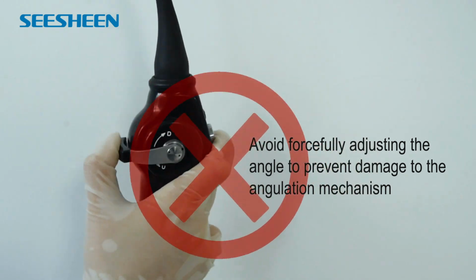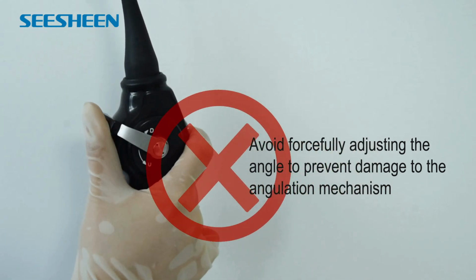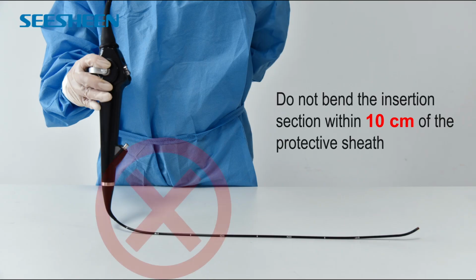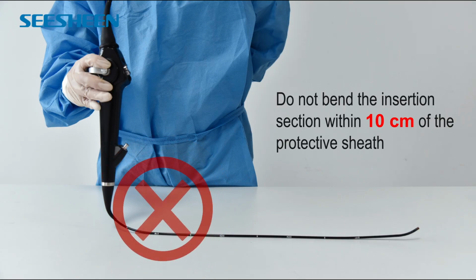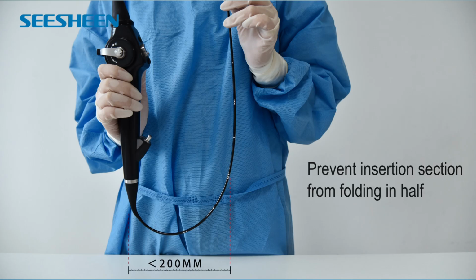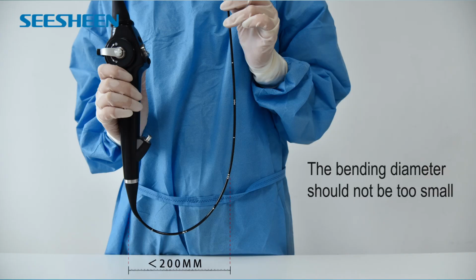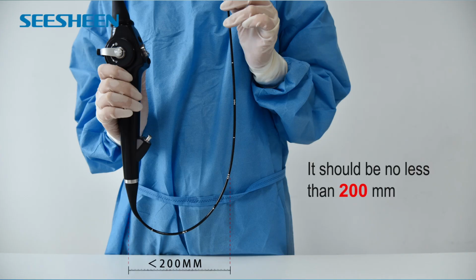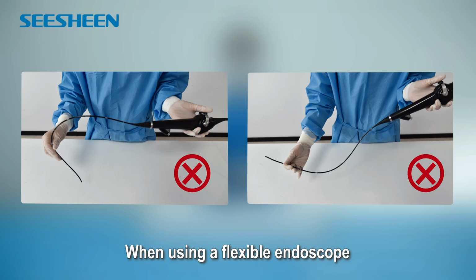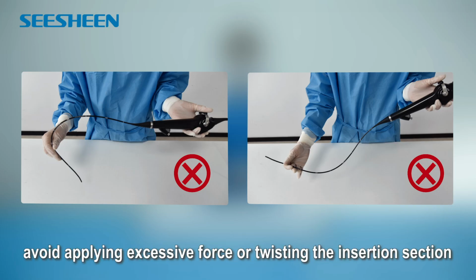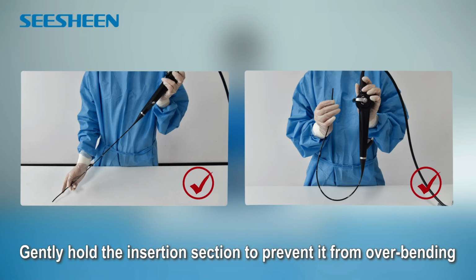Precautions for the operation section. Avoid forcefully adjusting the angle to prevent damage to the angulation mechanism. Do not bend the insertion section within 10 cm of the protective sheath. Prevent the insertion section from folding in half. The bending diameter should not be too small. It should be no less than 200 mm. When using a flexible endoscope, avoid applying excessive force or twisting the insertion section. Gently hold the insertion section to prevent it from overbending.